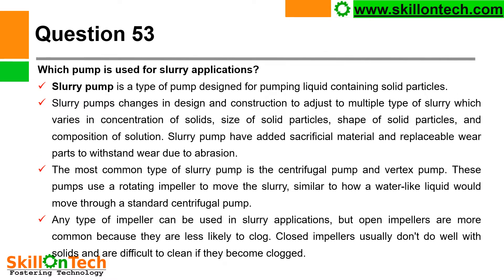Question 53: Which pump is used for slurry applications? A slurry pump is a type of pump designed for pumping liquid containing solid particles. Slurry pumps vary in design and construction to handle multiple types of slurry, which differs in concentration of solids, size of solid particles, shape of solid particles, and composition of solution. Slurry pumps have added sacrificial material and replaceable wear parts to withstand wear due to abrasion. The most common types are centrifugal pumps and vortex pumps, which use a rotating impeller to move the slurry. Any type of impeller can be used, but open impellers are more common because they are less likely to clog.